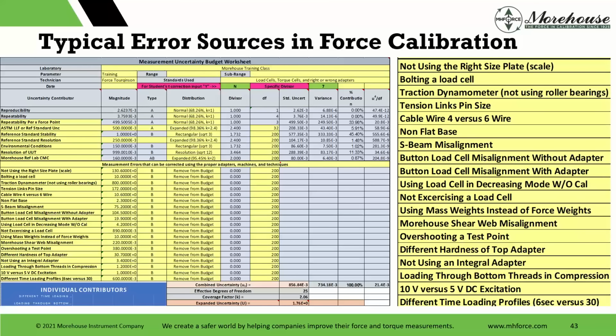So we talked a lot about safety. Hopefully there were some takeaways, and there are also all these other errors when it comes to force calibration. I like to sum them up in basically one sheet. I have this uncertainty budget here to show some things to be aware of: different loading profiles, 10 volt versus 5 volt, different excitations, overshooting a test point. And you'll find blogs, or if you've had our force training classes, we cover all of this and more: using a load cell in decreasing mode without having it calibrated there. Tension link pin size, we talked about that today. We talked about hardness and different hardness top adapters today. Shear web load cells, not using the adapter that was installed in them or trying to take it out and make a measurement. All of these things can impact the measurement result, and some of them can impact the safety as well.